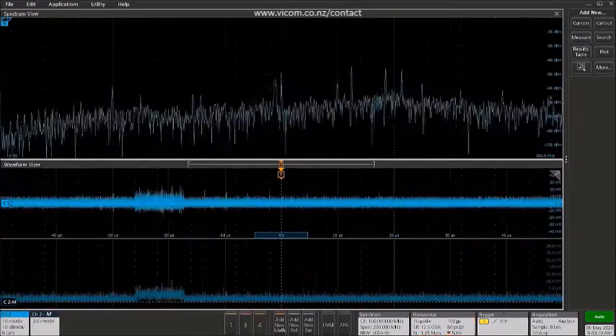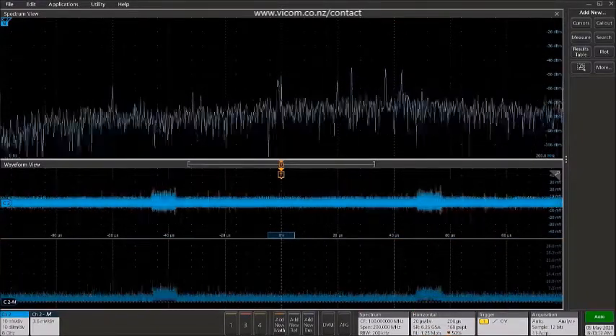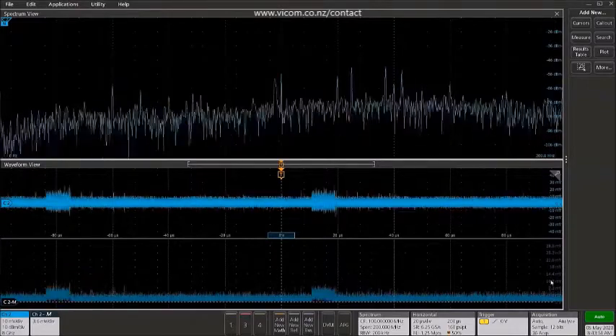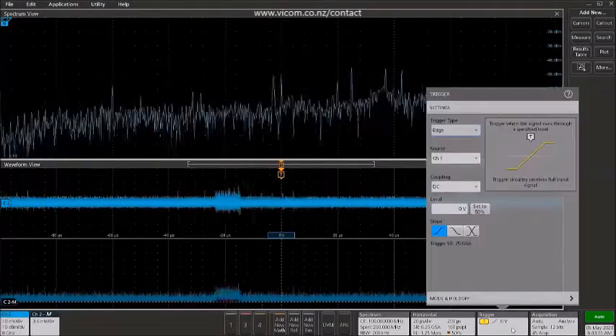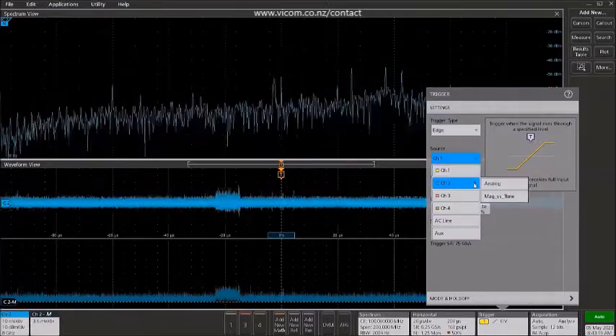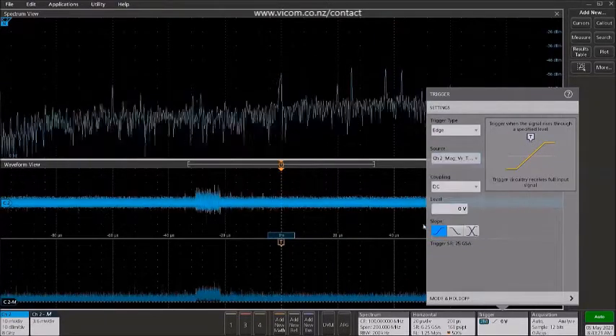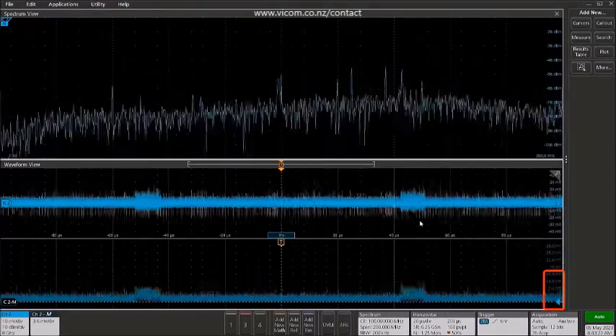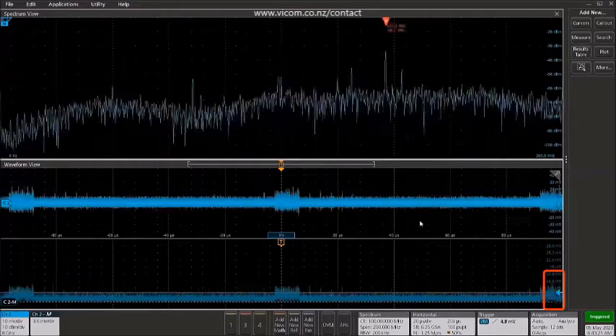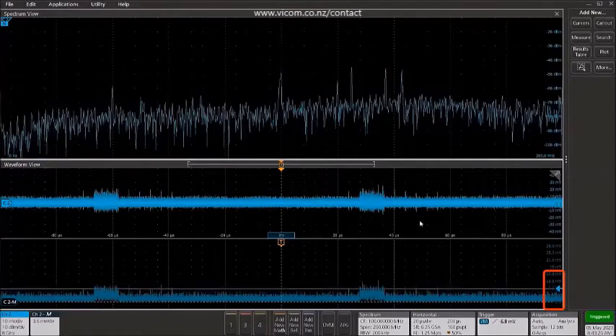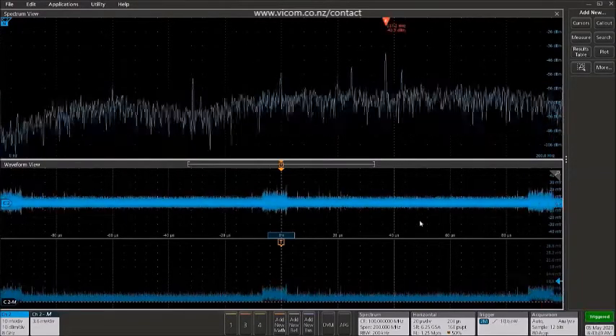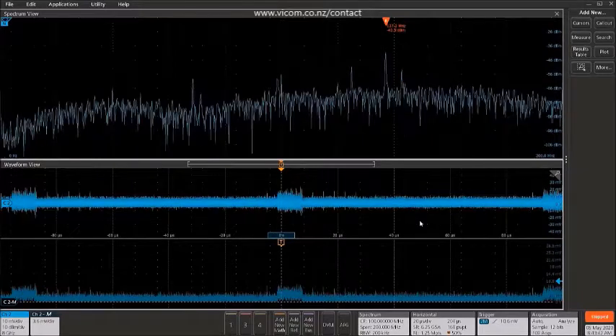And then it may be helpful also to enable a trigger, but let's trigger on the RF magnitude versus time. So I'm going to set the source to trigger to magnitude versus time, and we can adjust our trigger level to trigger just on this RF peak that we see. And we'll pause the instrument for a moment here.